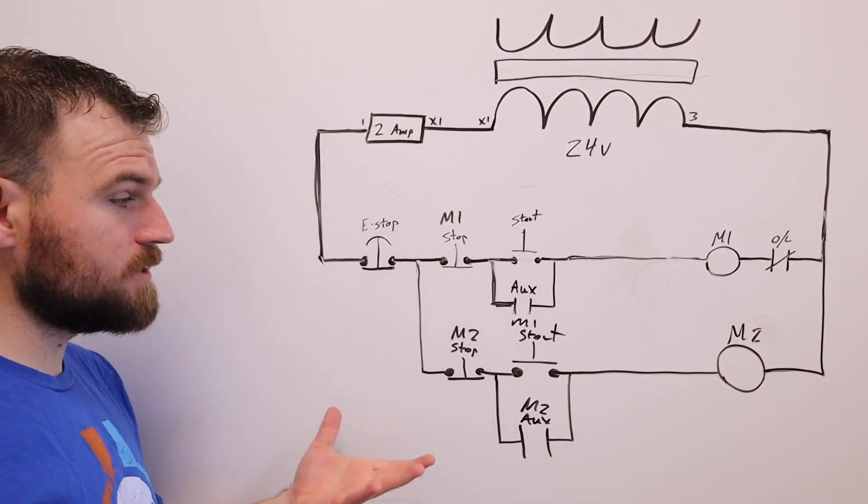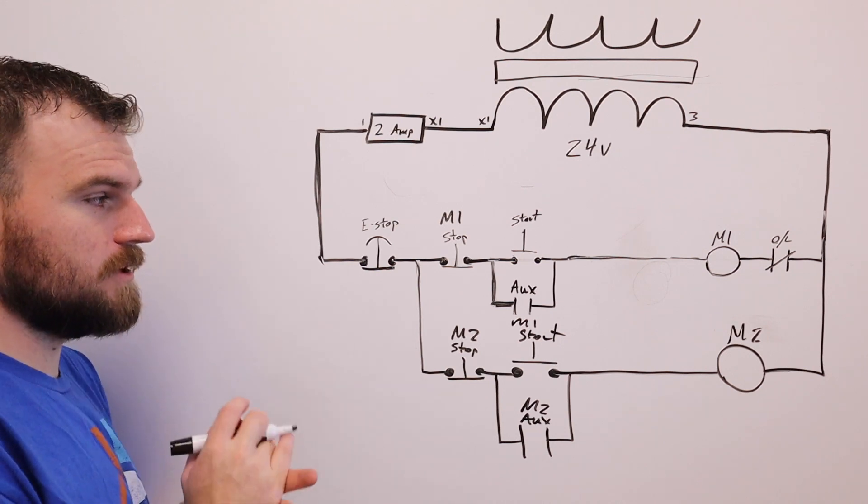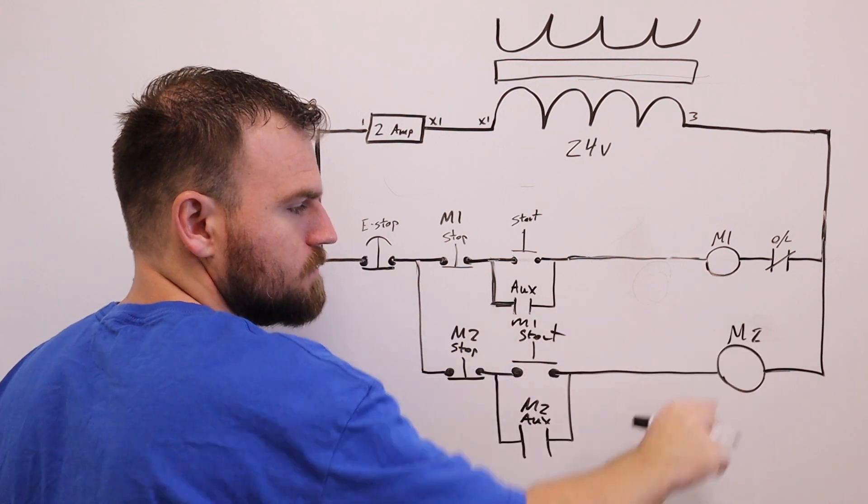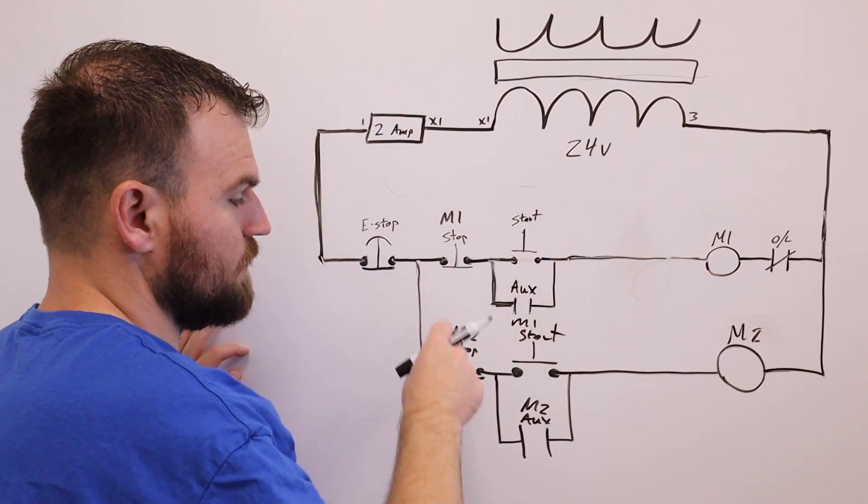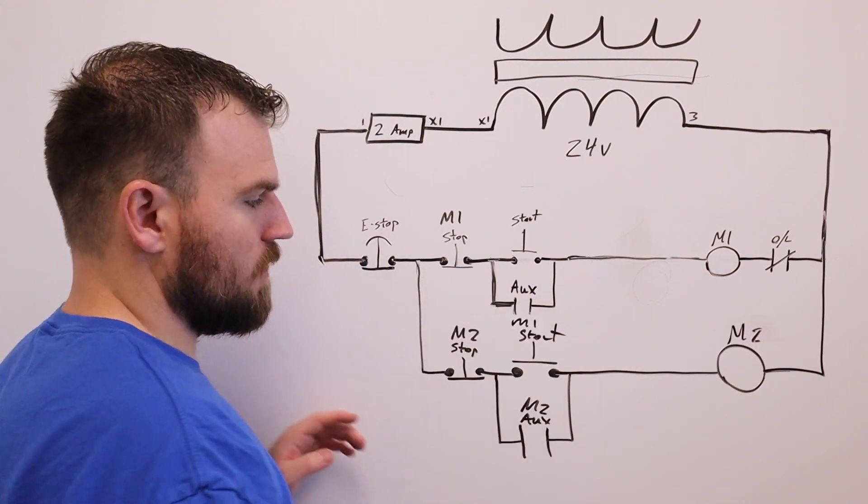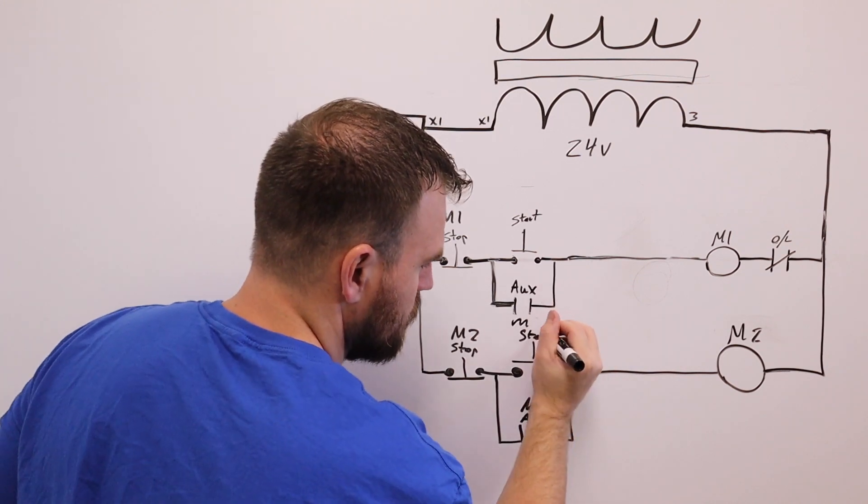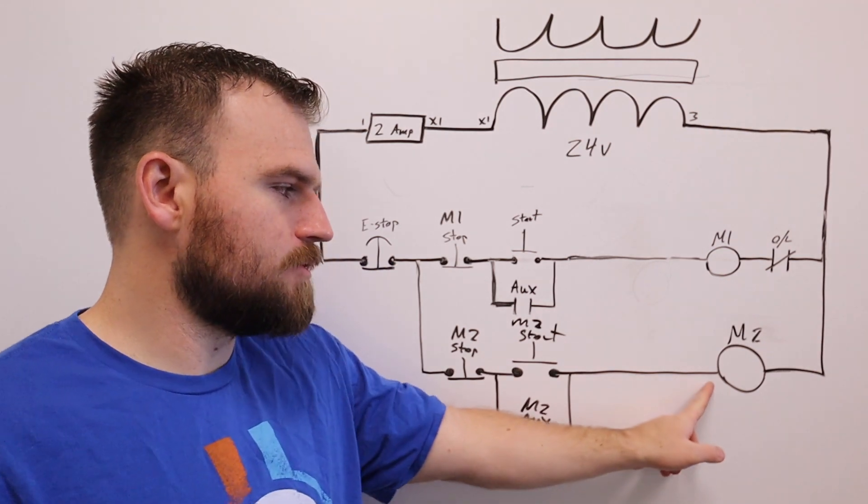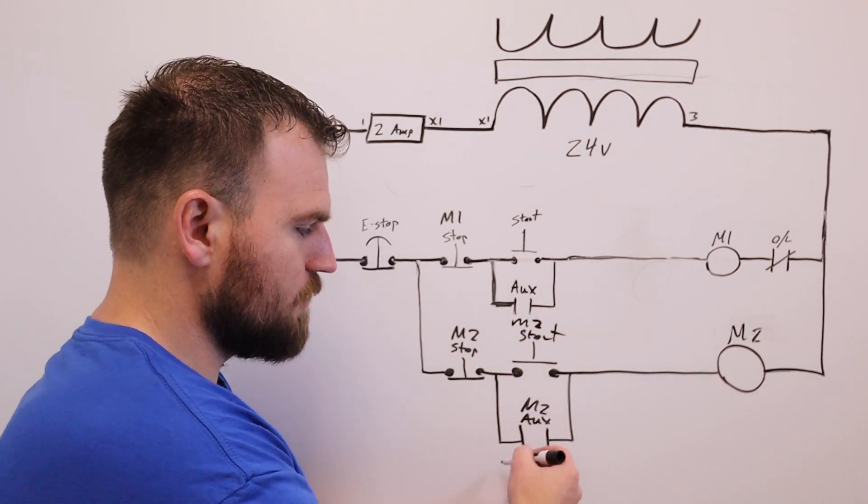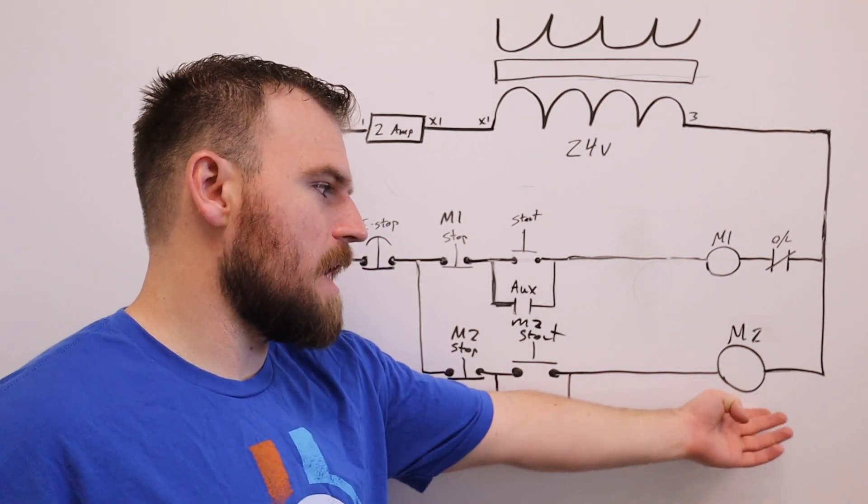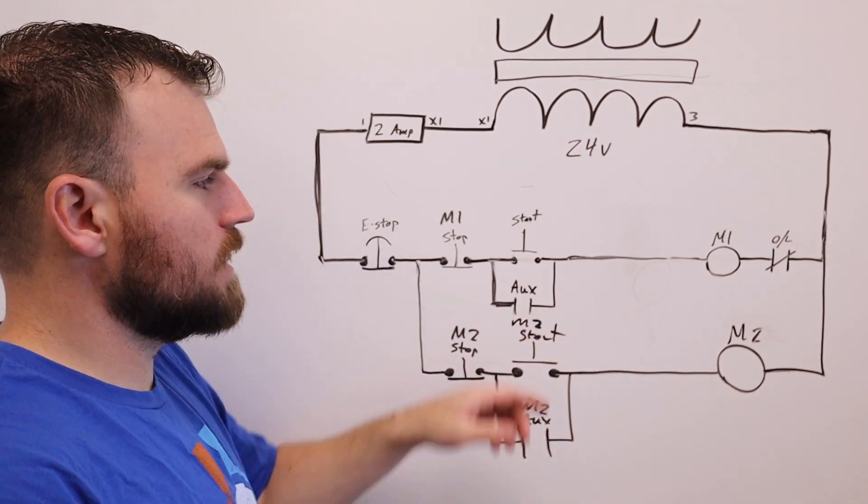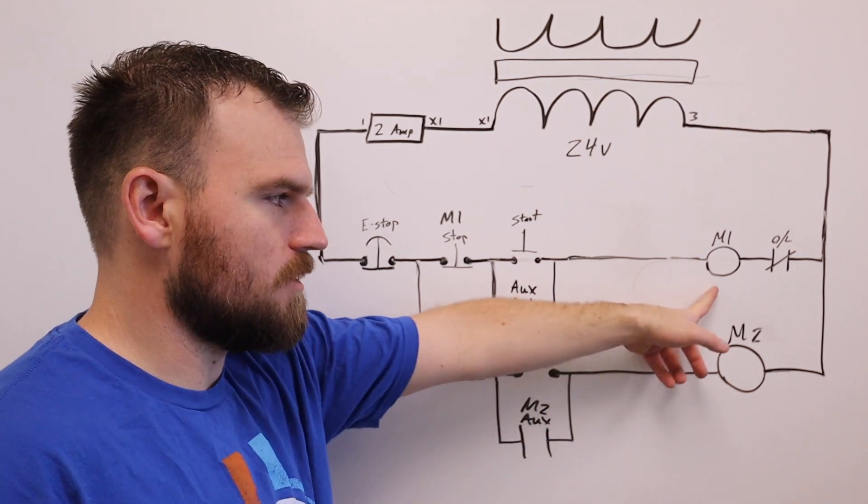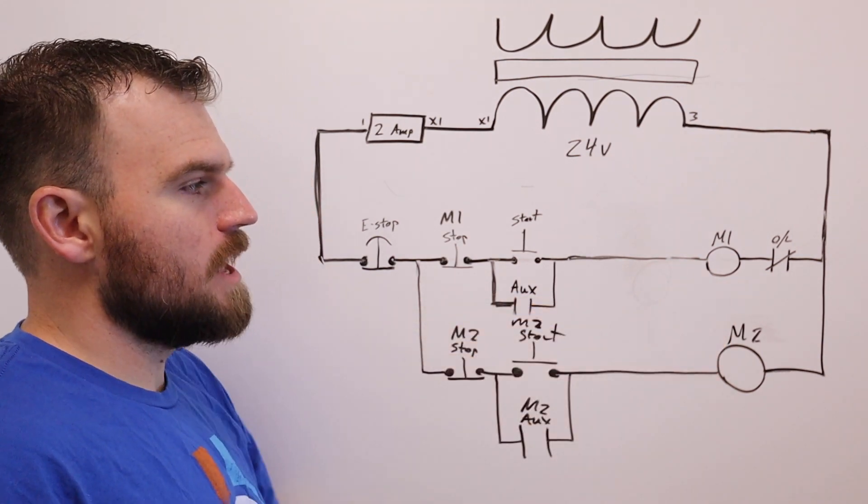That is pretty much the whole circuit - that's all we're going to be doing today. If you press the e-stop, there will be no power going to either one of these motor coils. If you were to press the start for M2, it will turn on the M2 coil, which will cause the auxiliary here to close and then keep M2 running. They're totally independent, so if I press the start button here, it's not going to turn on this rung down here - it's going to turn on motor one.